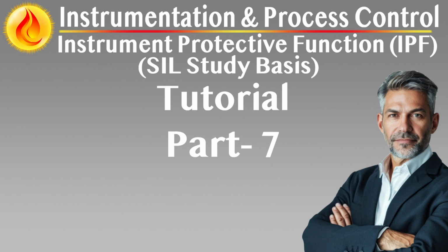Test coverage and effectiveness. Each test must demonstrate that the safety function operates as designed. If the test does not cover the full loop, the PFDavg calculation must be adjusted to reflect reduced test coverage.